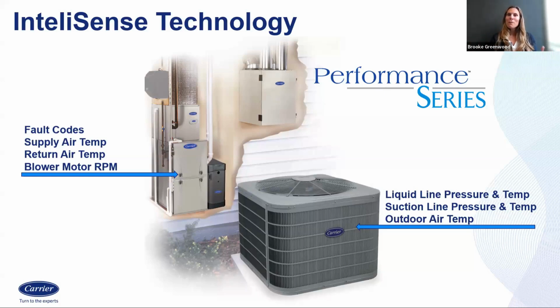You'll also see blower RPM feedback - that's another item that's coming as well. I won't go into a lot of detail, but I get pretty excited talking about all our products and launches. On your outdoor side, you're going to see your liquid line pressure and temperatures, and your suction line pressure and temperatures, so you'll get calculated subcooling and superheat values shown in the app as well.